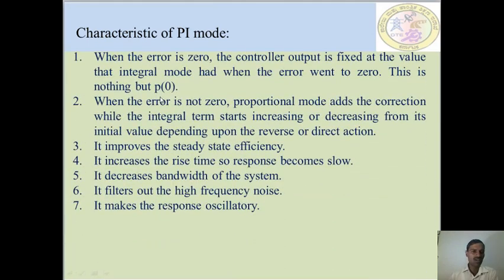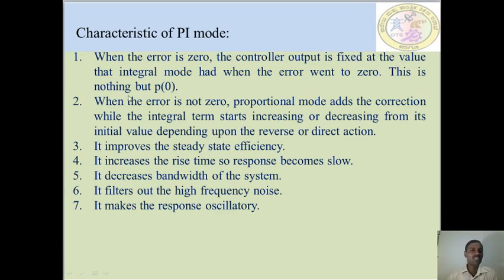The characteristics of the proportional integral mode controller are as follows. First, when the error is zero, the controller output is fixed at the value that the integral mode had when the error went to zero — this is P(0). Second, when the error is non-zero, the proportional mode adds the correction while the integral term starts increasing or decreasing from its initial value depending upon the reverse or direct action.